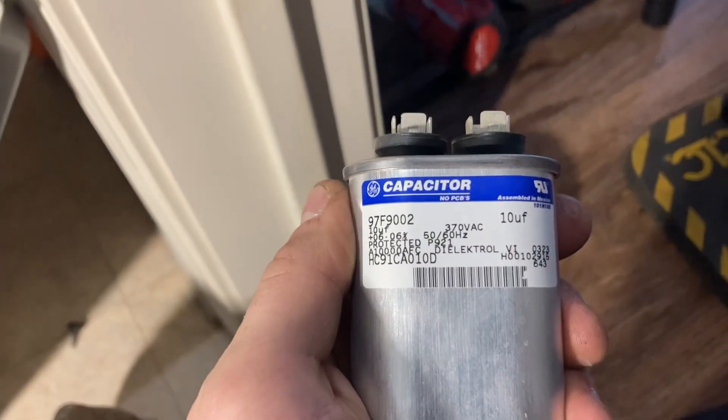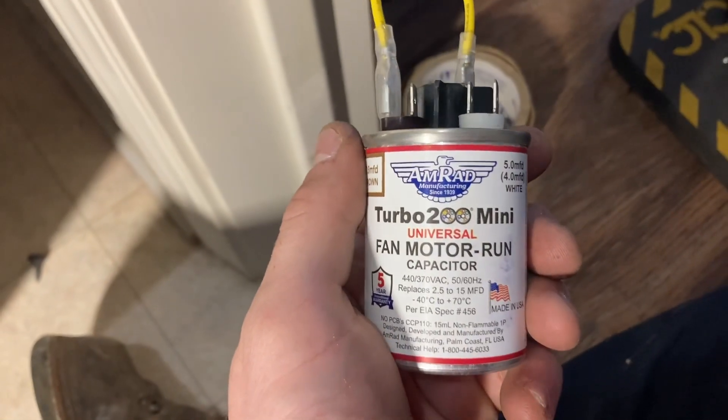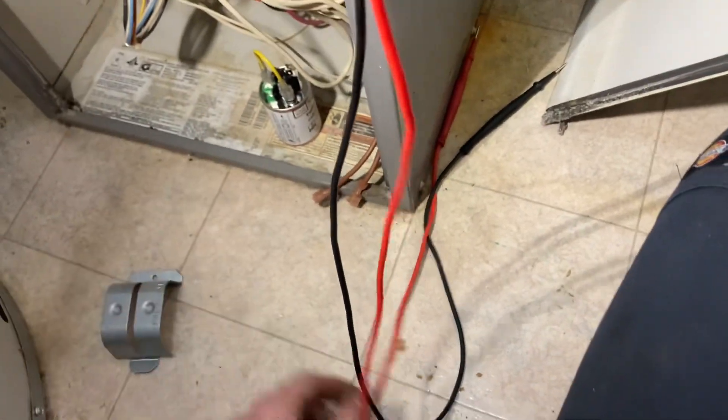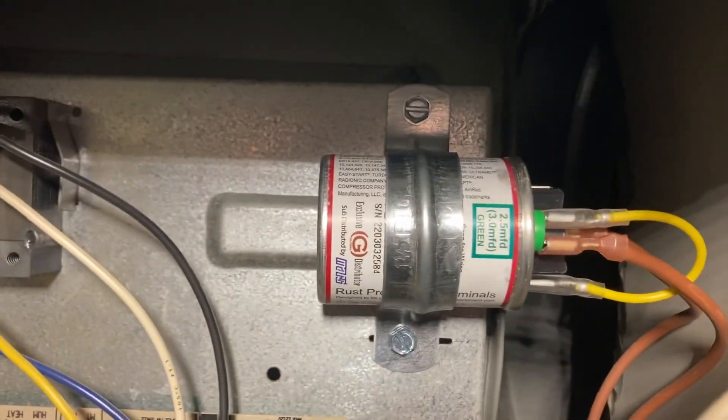This is a 10 microfarad capacitor, so we're going to change it out with a AMRAD Turbo 200 Mini. We have the big Turbo 200s too, and I always read the instructions on new stuff. What's 2.5 plus 7.5? Ten. We're going to put this little mini guy in there - secure it with a strap. Turbo 200 Mini strapped up nice.